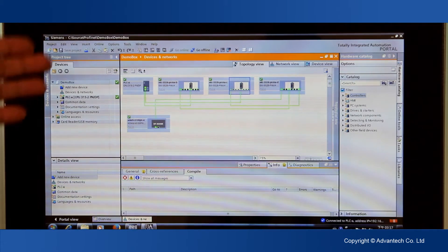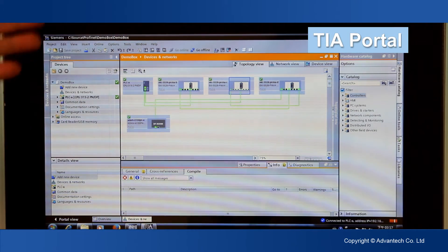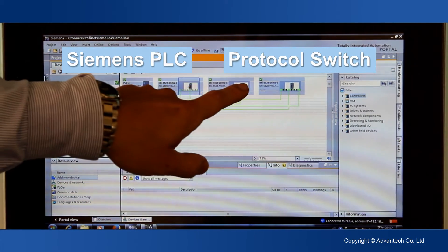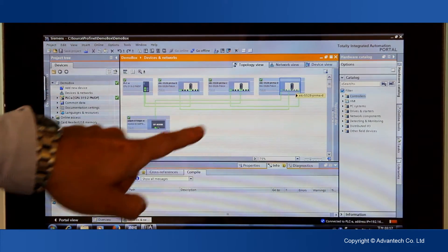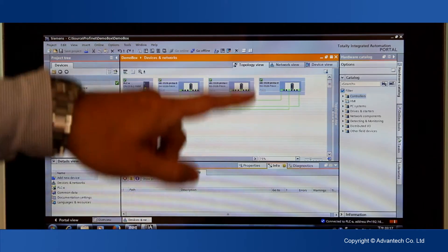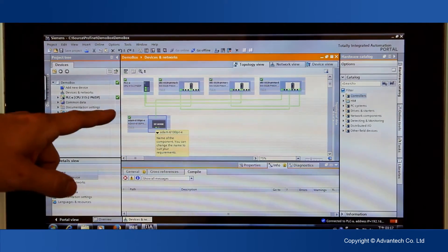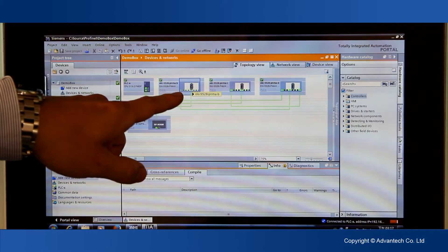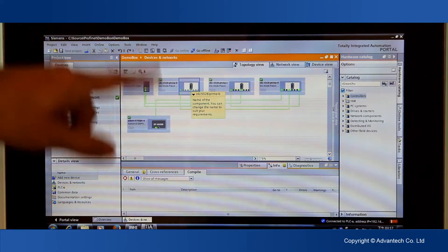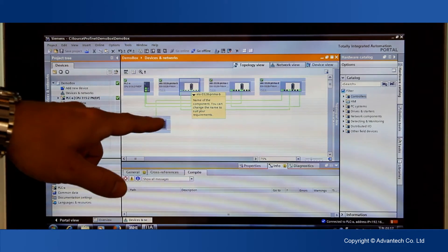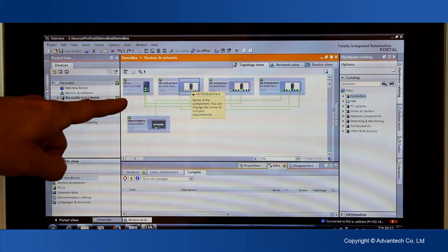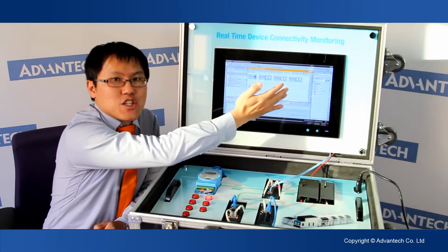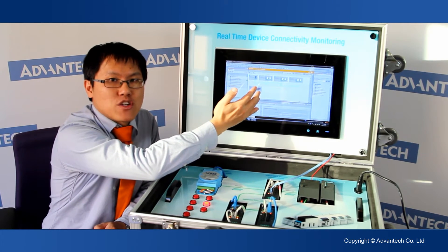We use the Siemens software TIA Portal to set up our environment. We can see we use the Siemens PLC combined with three of our protocol switches. And finally we use the ADAM data acquisition to set up this demo box environment. We can easily check which devices and which port link to the next devices at which port. We can use this topology view to check if the connection is normal or not. Furthermore, we support Siemens Ring MRP under this environment. Besides topology view, we can choose the device view to check the device's information or status.